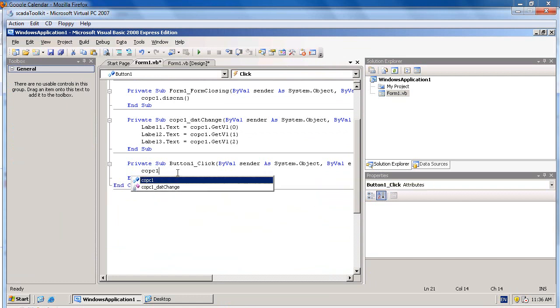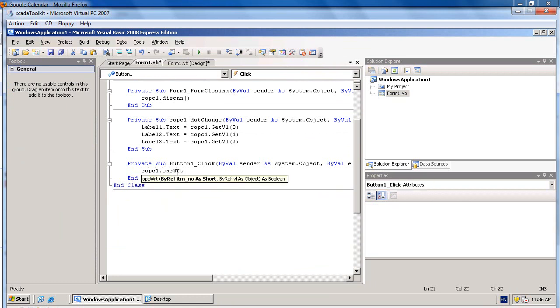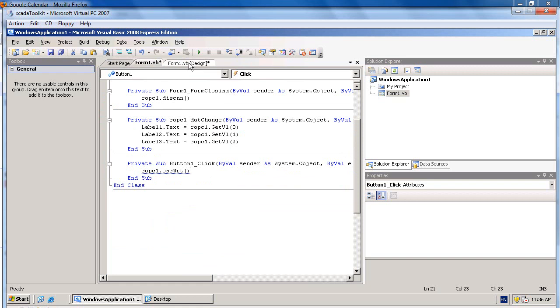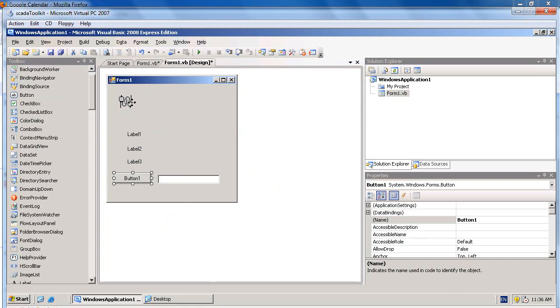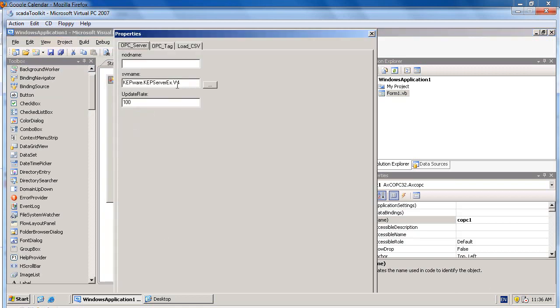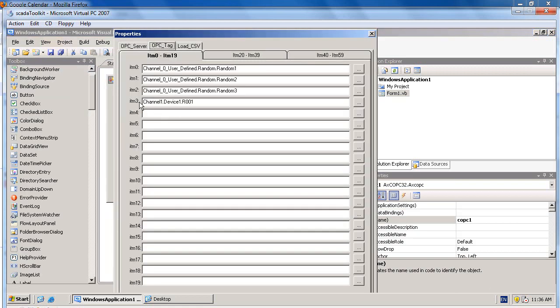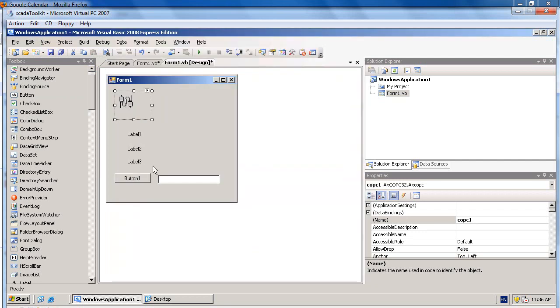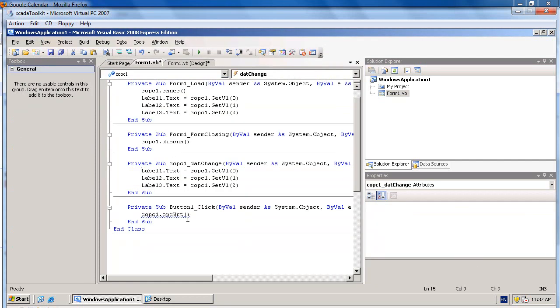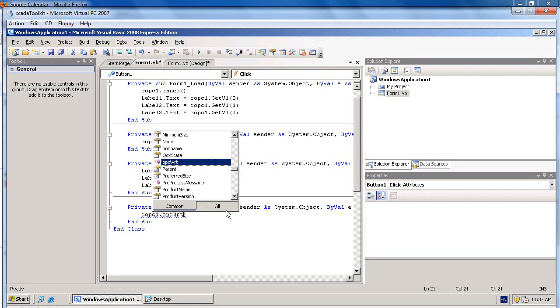Then, double-click on the button to write some command to send the value to OPC tags. So we use COPC1.OPCWrite. Specify the index number. If you cannot remember, get back to the form, right-click, select property and see OPC tag index number is 3.